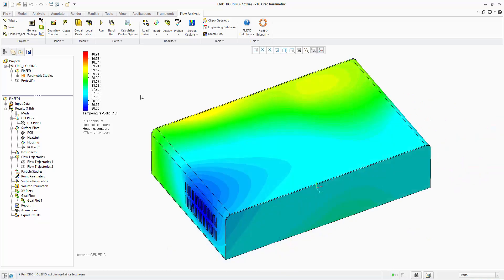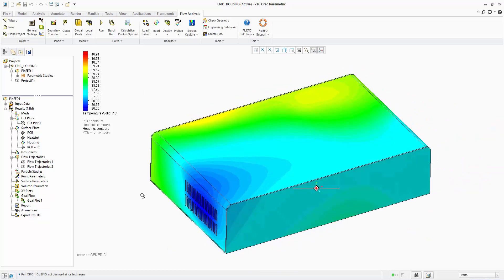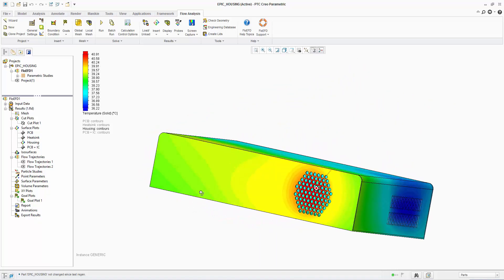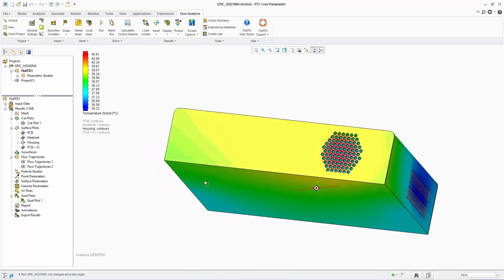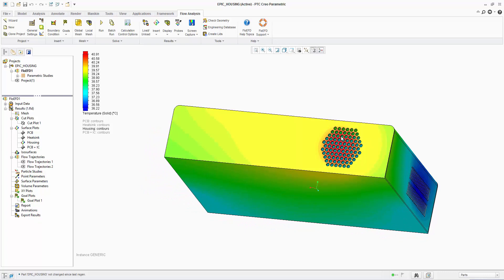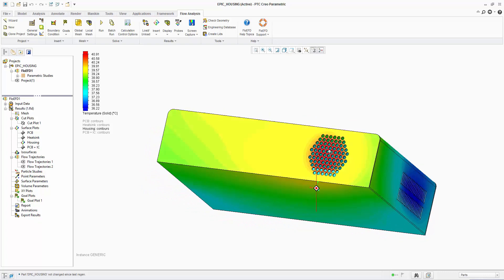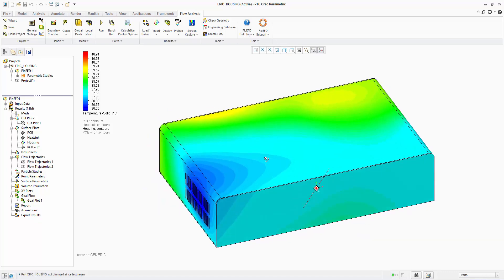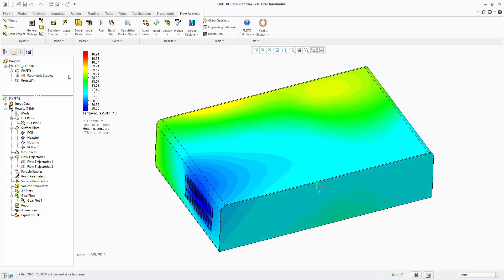The enclosure temperature shows us if our electronics will pass touch temperature compliance. Our model squeaks in at just under 41C around the fan outlet, which is a typical industry upper bound.